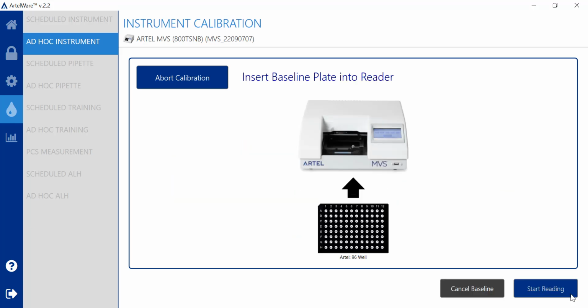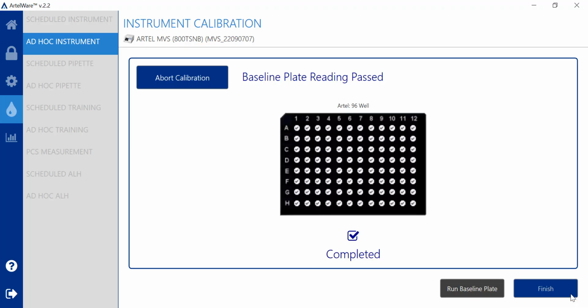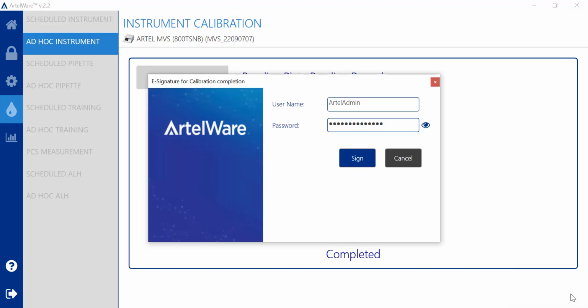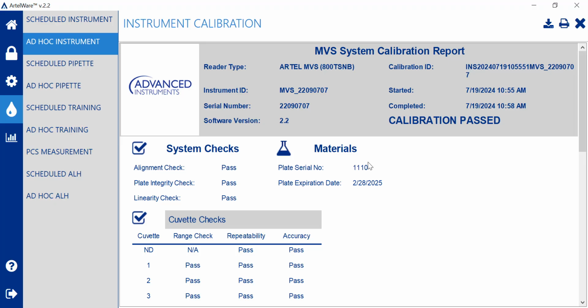The baseline plate shaking sequence is now complete, so I'll go ahead and insert the plate into the reader, and I'll click on Start Reading. The baseline reading has passed, and everything's completed, so now I'll go ahead and click on Finish. Because I have the Compliance Suite module add-on for my ArtelWare application, I'm being prompted to enter an electronic signature. Once my electronic signature has been entered, I can now view the system calibration report.